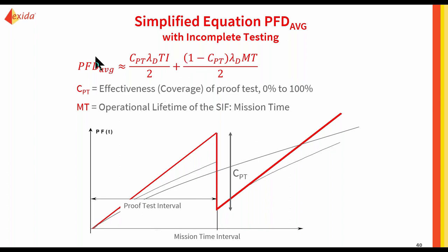So in that case, first of all, maintenance, you need to do proof tests more frequently. And then you also need to change out or overhaul your equipment more frequently if you have a higher SIL level than is actually required in a realistic sense. So that's why it's going to create a lot of cost, a lot of drainage of resources for you whenever you overestimate the SIL level.